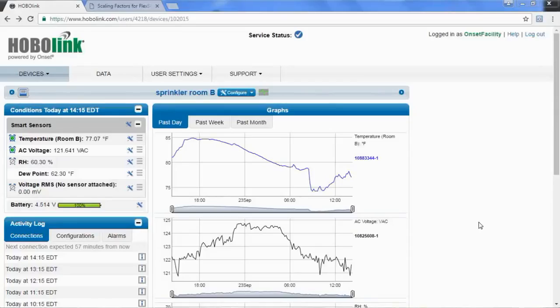Here we have the HOBOlink page for this monitoring system, where we're monitoring temperature, relative humidity, and that AC voltage. In order to use that AC voltage measurement, we need to scale the input to that TRMS module. So here's my AC voltage channel right here. See, it's reading about 121 volts AC. We're in the US, so we expect it to be around 120. To get into the scaling for that, click on the little icon here, the little screwdriver and wrench, and it will say configure this sensor. We'll click on that.